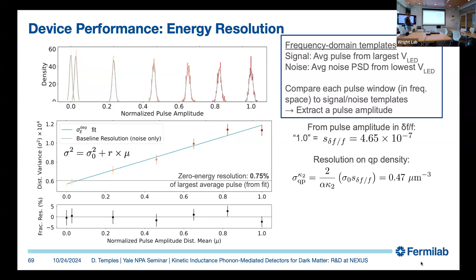So once we have extracted the pulse amplitude for each window in each LED setting, we construct these distributions. We extract the width and the mean of each of these. And we plot the variance versus the mean, and we see it follows this line as we expect. From this, we can then extract the fit parameters sigma naught and R. And so from this fit, we determine that our resolution on the quasi-particle density fluctuations as measured by the frequency direction is about half a quasi-particle per cubic micron, which is well in line with what we estimated ahead of time.